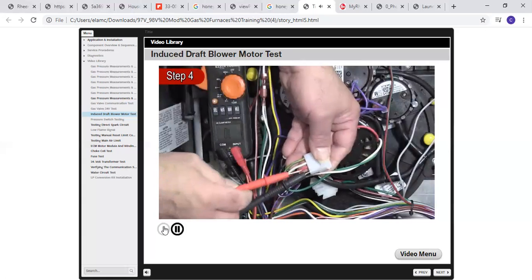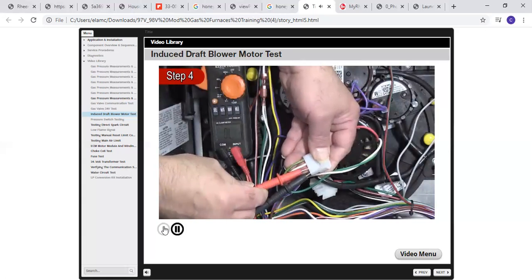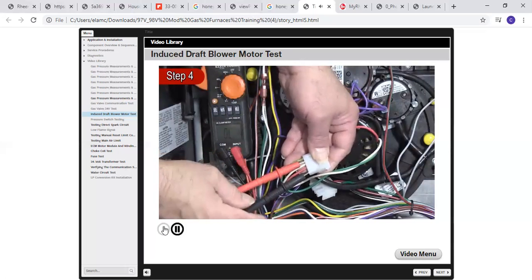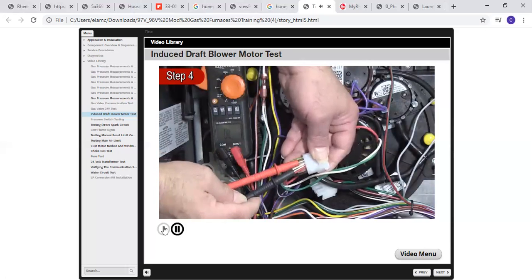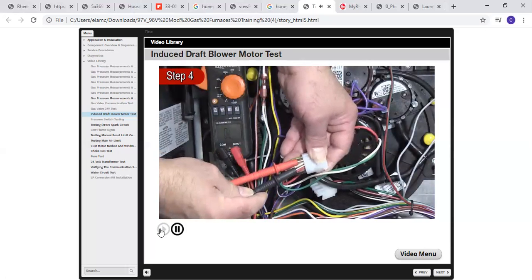If all of the readings are infinite ohms, the internal motor overload is open. Allow time for it to cool and reset. If any of the readings vary from other combinations, the motor is defective. Replace the motor. If everything checks out okay, continue to the next step.